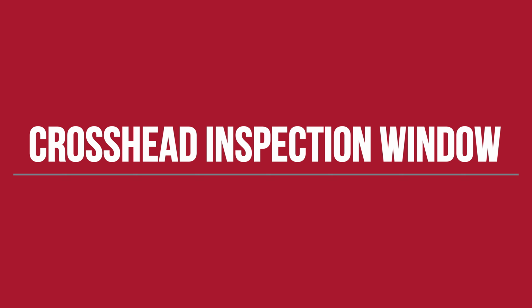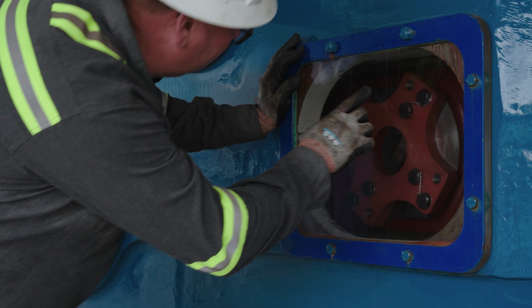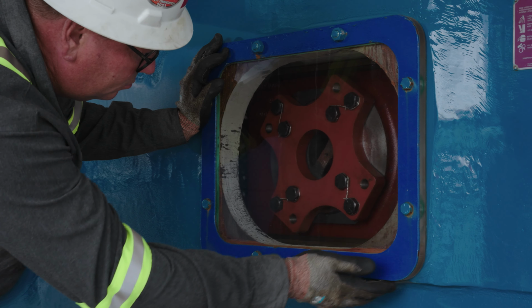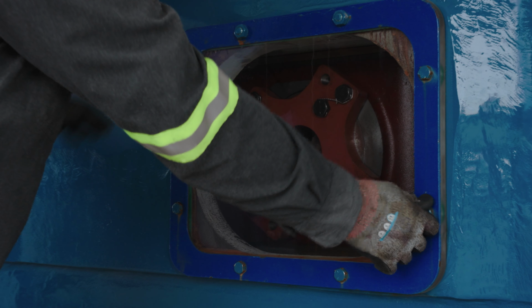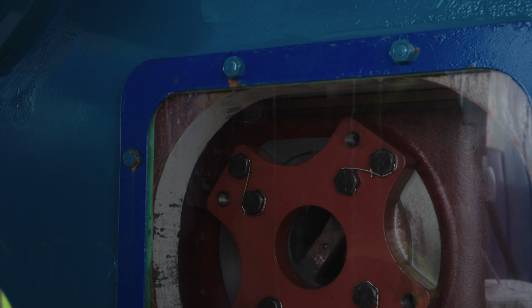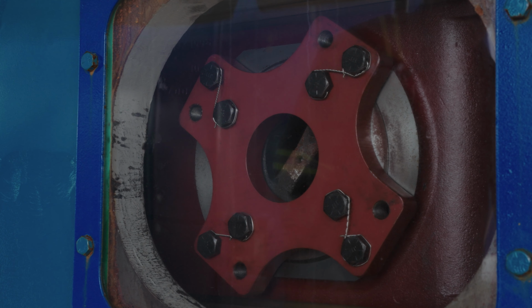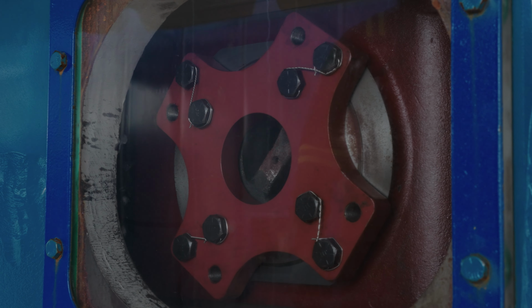Moving to the pump, we have a crosshead inspection window on both sides of the pump. Make sure to inspect both sides of the pump. You need to make sure it's clean so you can visually check your crossheads, slides, pony rods, and internal spray bar system. Visually check inside.